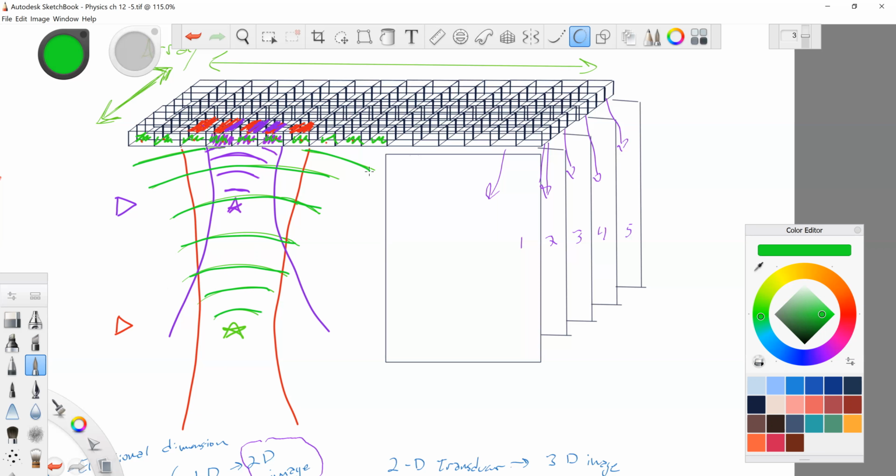And rather than listening with the same number of elements that created the beam, manufacturers said, you know what, when it comes from, let's just make up a number, 39 microseconds or 3 centimeters away, we might use 5 elements to create that sound beam, but we're going to listen with 10 elements because we know the sound beam spreads out.